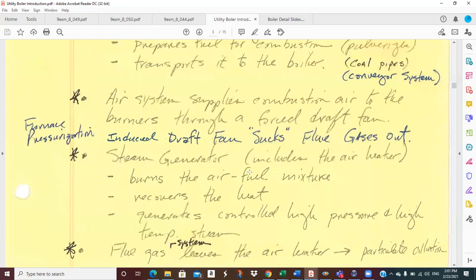It's awful. Who in the world would design a power plant to pull all of your fly ash through your induced draft fan? It's lunacy, but it happened. And that plant was opened in like 1953. They've been fighting this thing for almost 70 years. It still operates, and they still fight it, because they've looked several times at moving the fans, but then the fans are not sized right. They'd have to replace all the fans. It's a multi-million dollar thing to start moving those fans around. And so they just grin and bear it and keep repairing the fans. Okay, enough of a walk down memory lane.